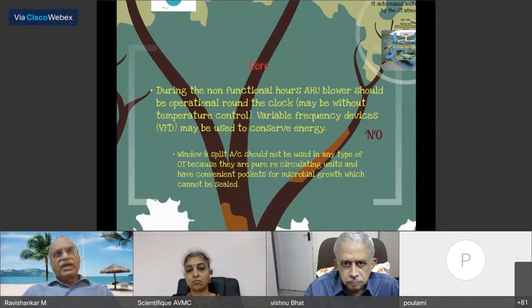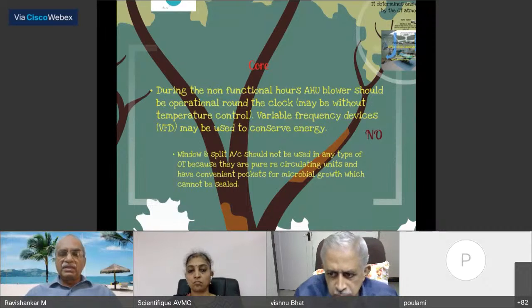But quite often what we find is in all our theaters, when we close, everything is switched off, locked up and gone. That is not right, because when there is just heating up inside, there will be condensation of water in every place, and then it will promote growth of organisms. That is why the requirement is that the air handling unit should not be put off, and the control can be reduced.